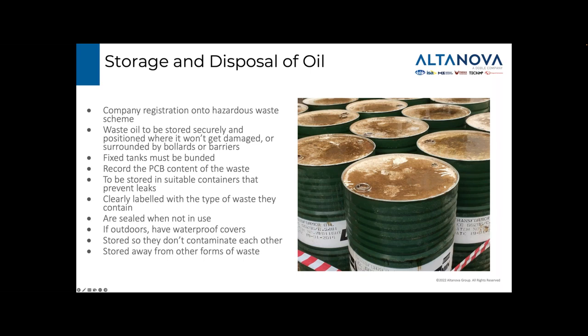In order to meet the requirement of your local legislation, oil needs to be stored securely and somewhere safe in a bunded location. If your country has a PCB legacy issue, polychlorinated biphenyls, like we have here in the UK, PCB content may need to be provided prior to collection. The storage containers need to be of sound construction, prevent leaks, and also be labelled clearly with their contents and sealed with the correct bungs. The containers should be covered if left outdoors and stored in a way that prevents cross-contamination from other oils or chemicals or to the environment, and also protects them from damage from moving equipment.